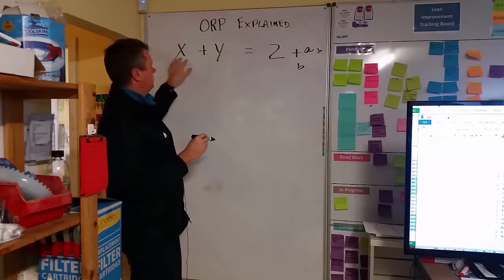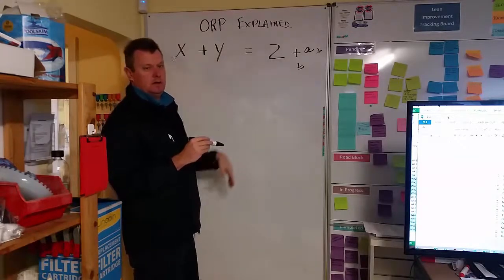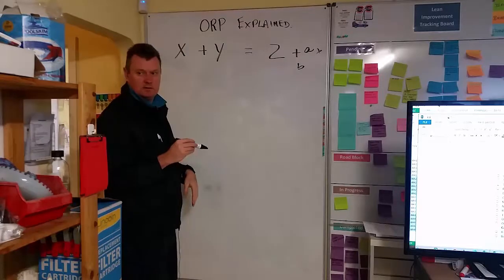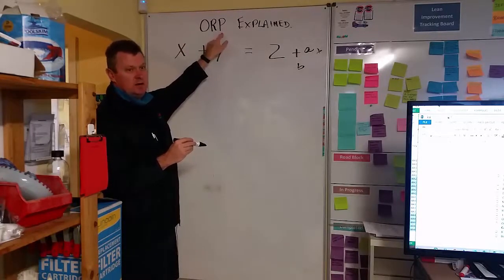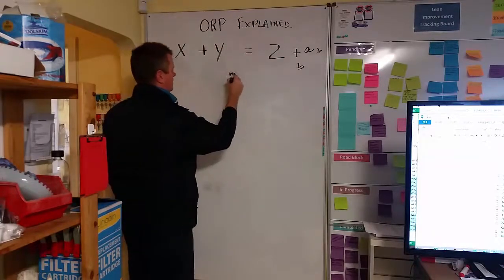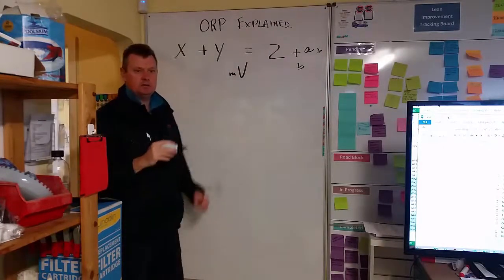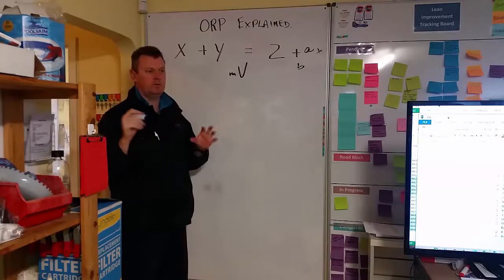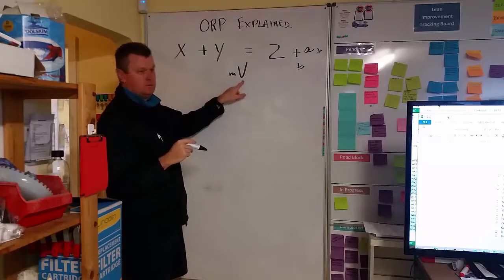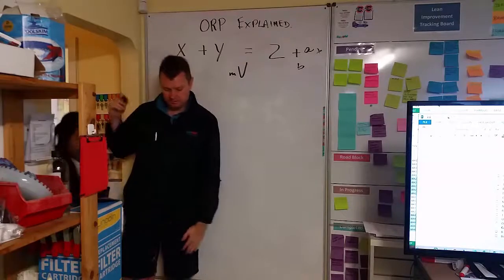Chlorine operates chlorine plus bugs or whatever equals blah, blah, blah. Okay, so that's the ORP is the potential, so that's like the killing power of the water. So that's measured in millivolts, which is where the reading on the front of the screen is 705. It's not 7.05, it's 705 millivolts.